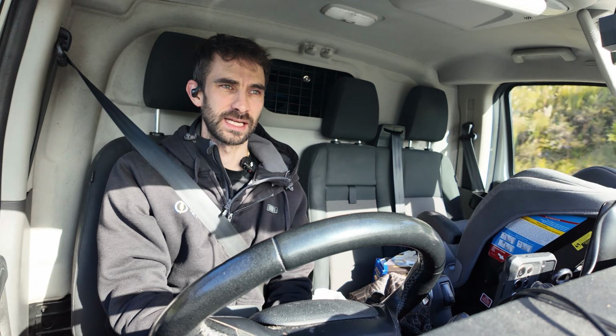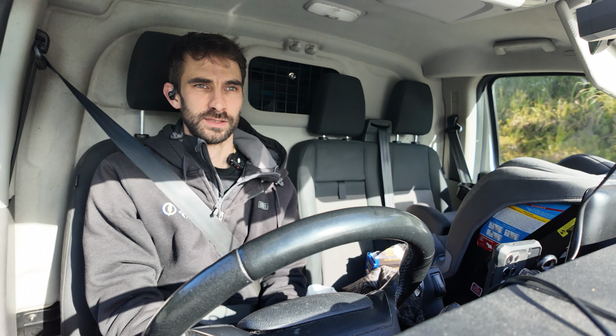In New Zealand, the regulations require short circuit protection to operate within 400 milliseconds, which I guess should be enough that if you're holding a metal device or touching a metal surface that becomes live from that fault, it's only live for 400 milliseconds, and that's not enough time for you to suffer damage.